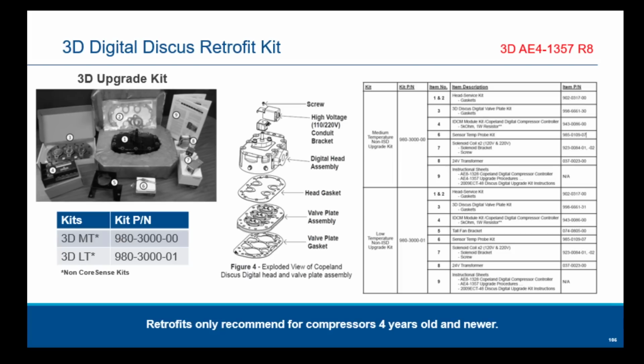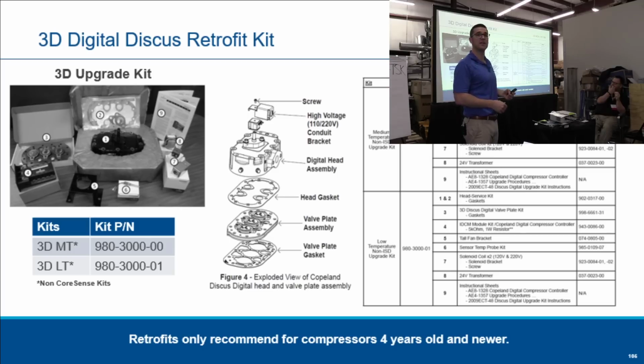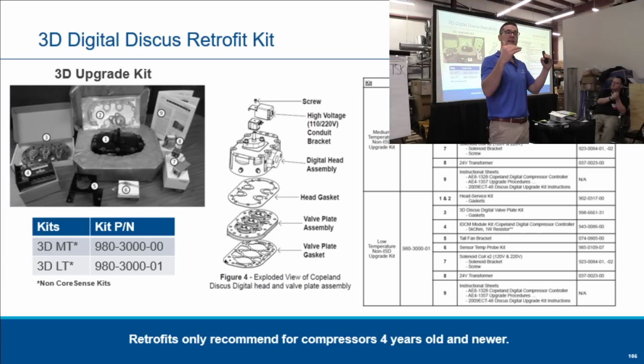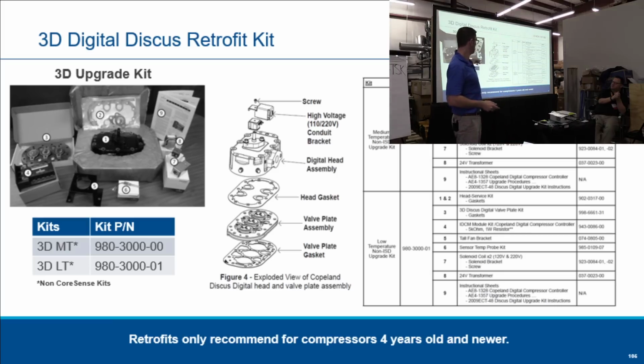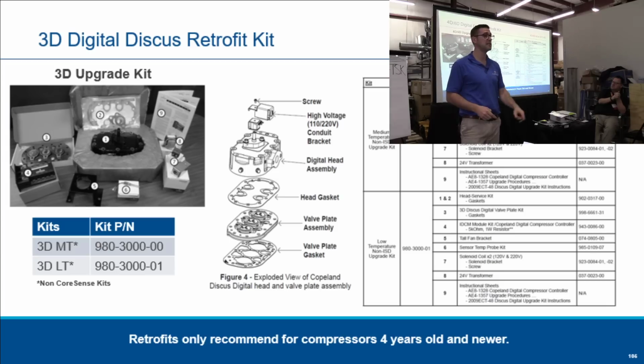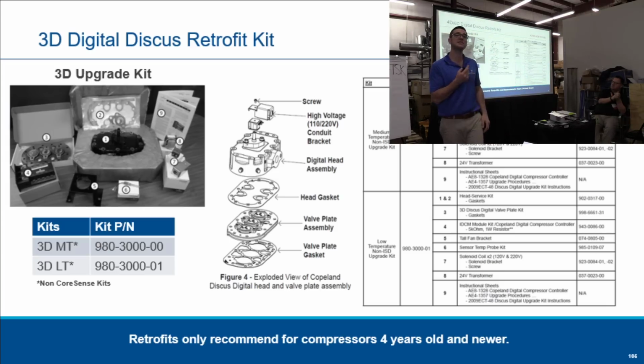So you could actually go to your wholesaler, talk to them, here's some part numbers, just say, listen, I have a multiple compressor application. I find that the capacity and the loading is not very good. We actually added a bunch of glass doors to 70 feet of 5 deck, right? Now all of a sudden that load is really low on that compressor system. So the compressor is banging on, banging off. Well, potentially you can retrofit to a digital compressor. Same with the 4 and 6Ds. Once again, application engineering bulletins, read them. See if that's the right solution for your customer.